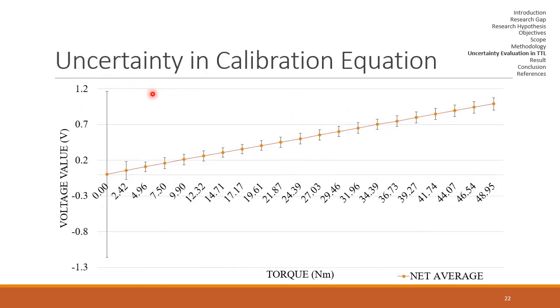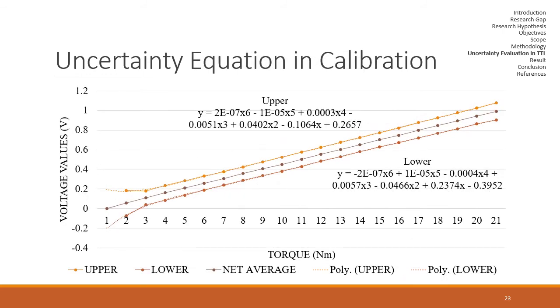Further, for the development of uncertainty in calibration equation, first of all, the uncertainty calculated in each point is plotted in the graph. Now we can see the variable uncertainty. For example, the uncertainty level at this point is greater than at this point. So the upper limit of the uncertainty and the lower limit of the uncertainty are joined so that to develop a new curve as shown in this figure.